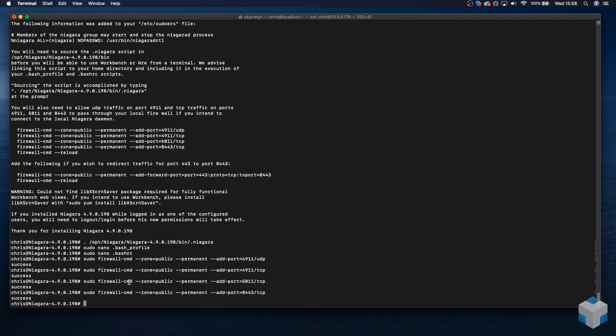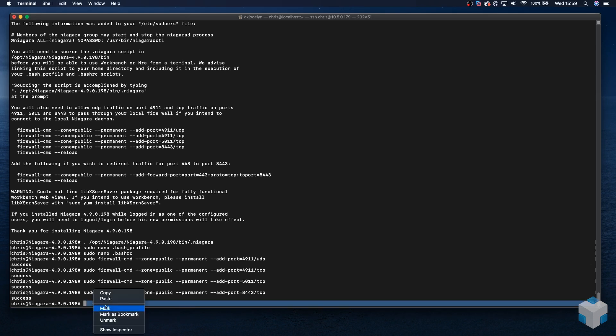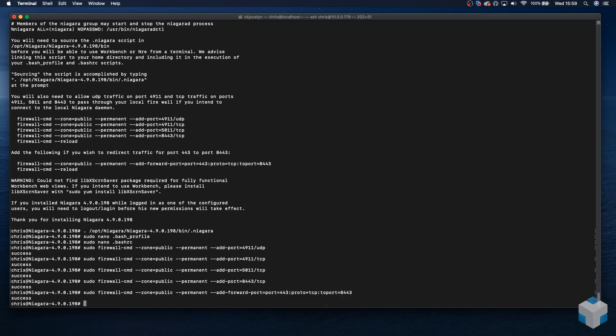This last firewall rule is a simple port forward from 443 to 8443. Since in Linux, the first 1000 ports are reserved for use by specific applications, our Niagara station will be unable to bind to 443. We can instead set our station HTTPS port to 8443 and use the firewall to forward incoming connections on 443 to do it. To do this, we just need to copy in another command, which is on my clipboard here. Paste, and that's successful.